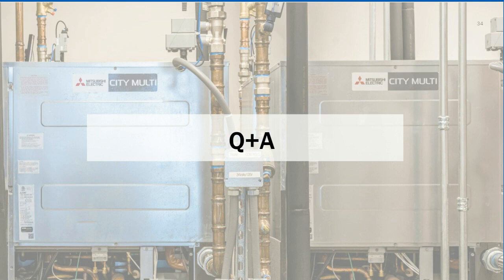The nice thing with water source is, like you've seen in some of the pictures, the condensers and everything are inside, easy to maintain. There really is minimal maintenance other than the water conditions, but once you get the condenser water system set up, it's closed loop, so it's just a matter of keeping that out of trouble. The maintenance on air source is very simple, really just cleaning the coils with water, just some basic stuff like that.